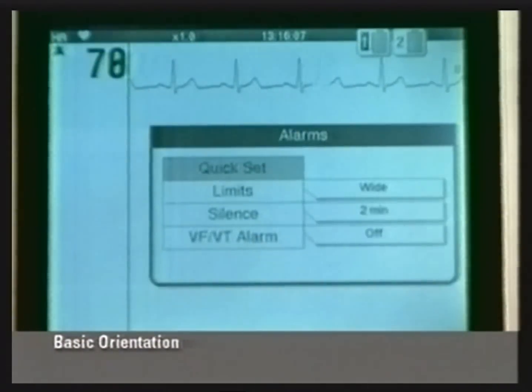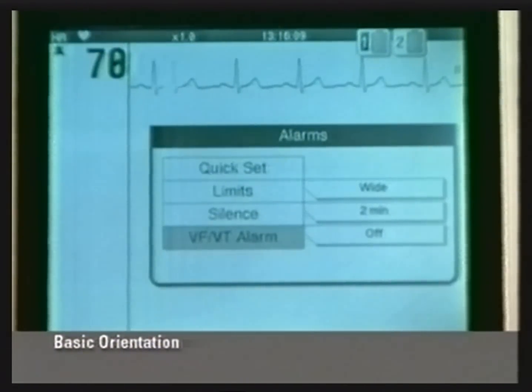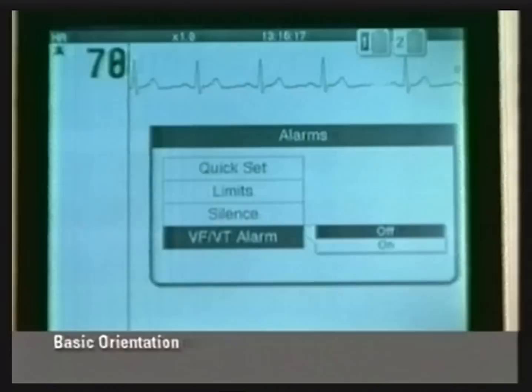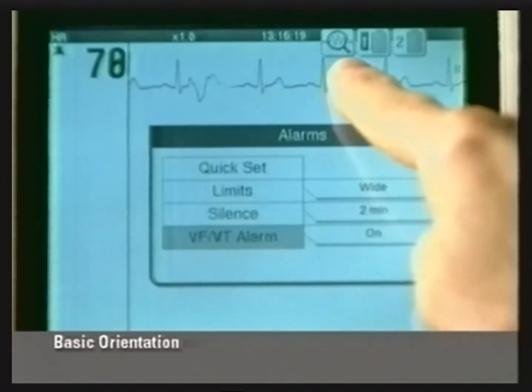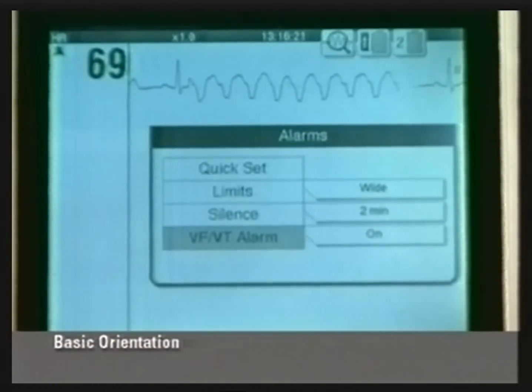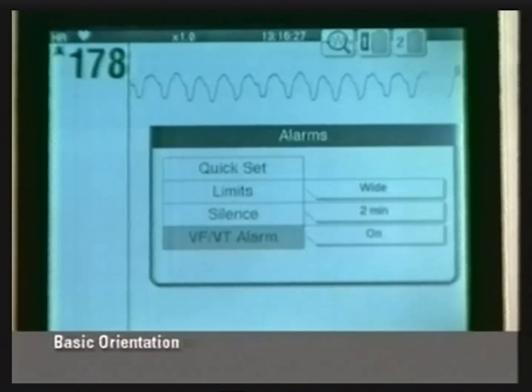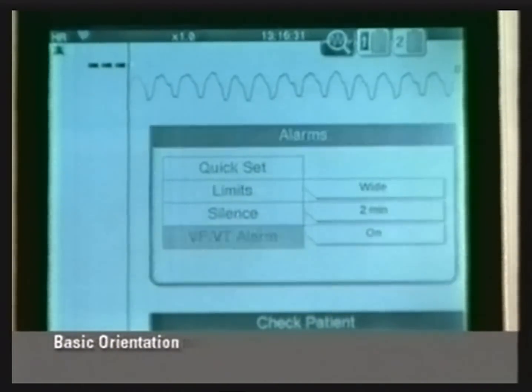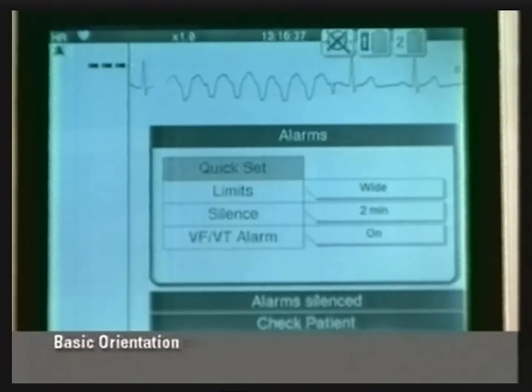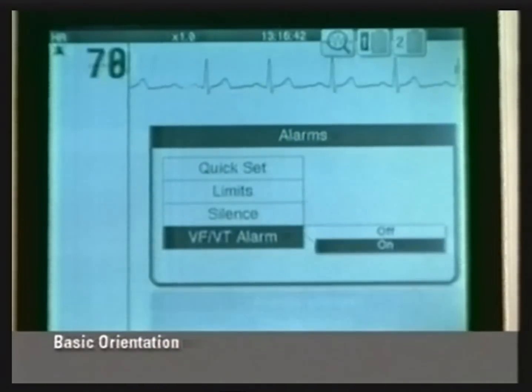In addition to the Quick-set feature, the VFVT alarm continuously monitors for ventricular fibrillation and ventricular tachycardia. When selected on, the alarm symbol appears above the primary ECG. When the VFVT alarm is silenced, an X appears over the symbol. Select Off to turn off this alarm.